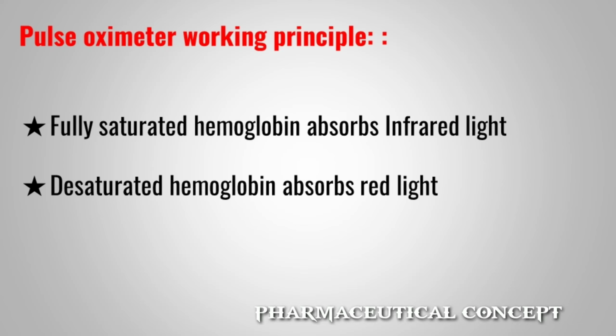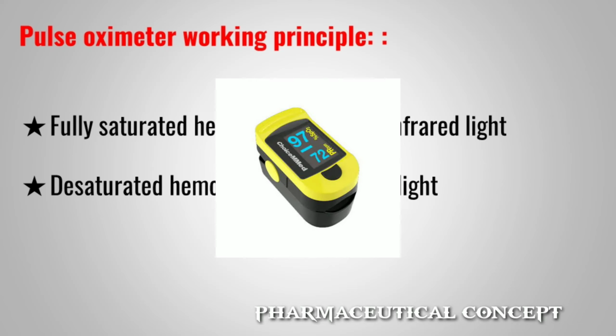As I mentioned earlier, two different lights, IR light and red light, are used. The fully saturated hemoglobin absorbs infrared light, and desaturated hemoglobin absorbs red light. Based on that, it calculates.